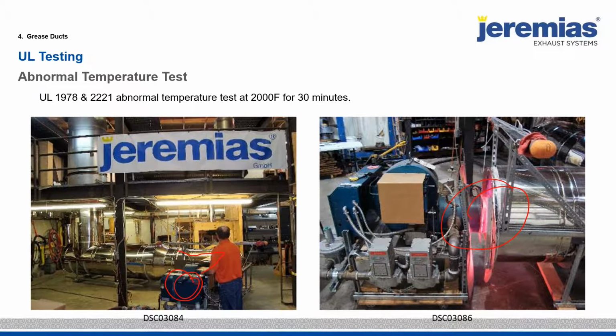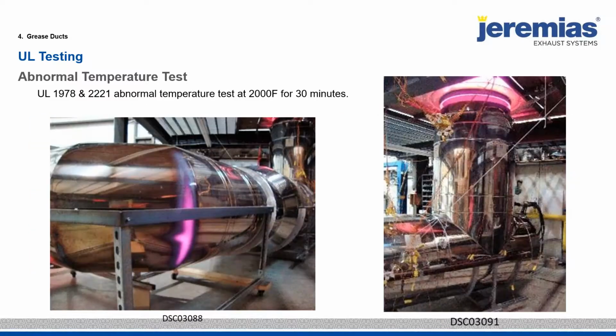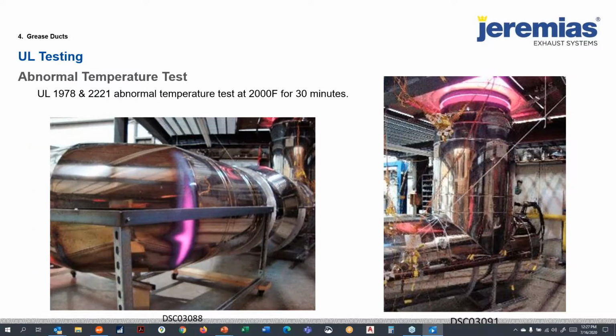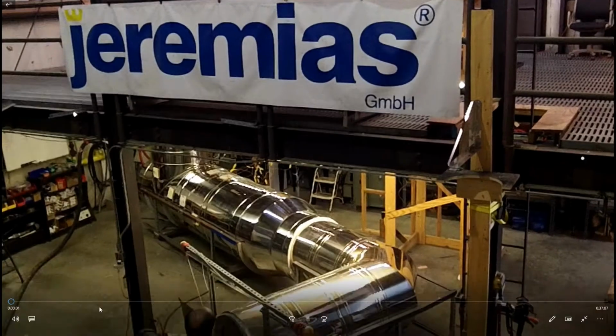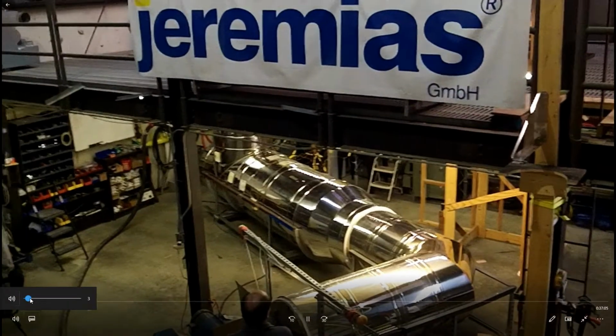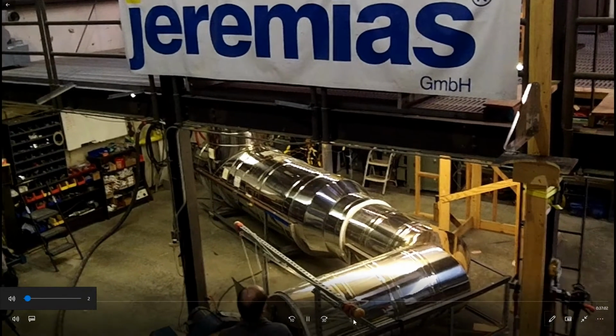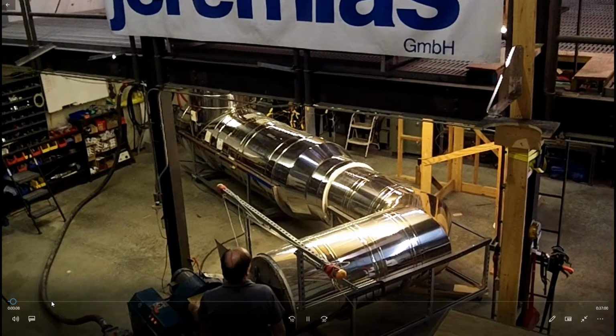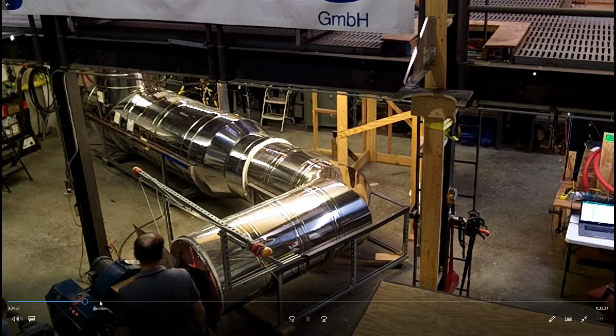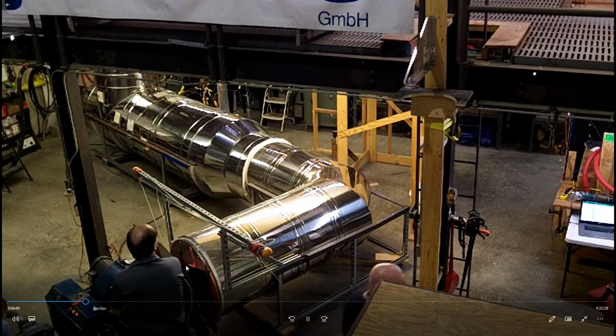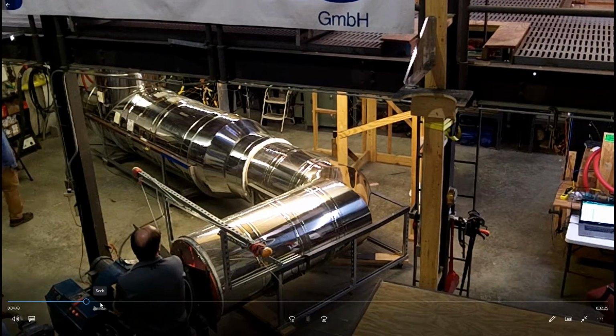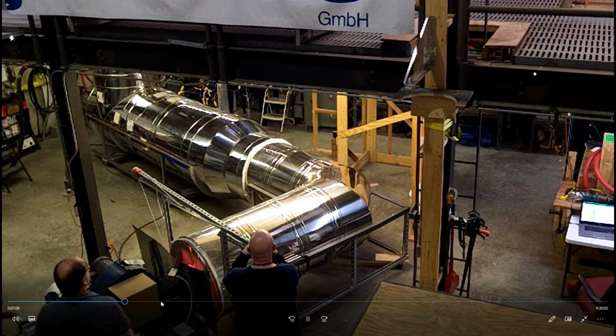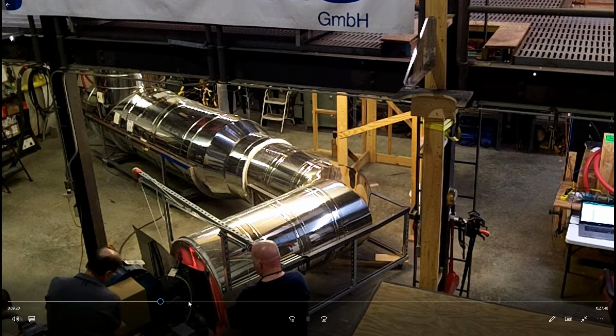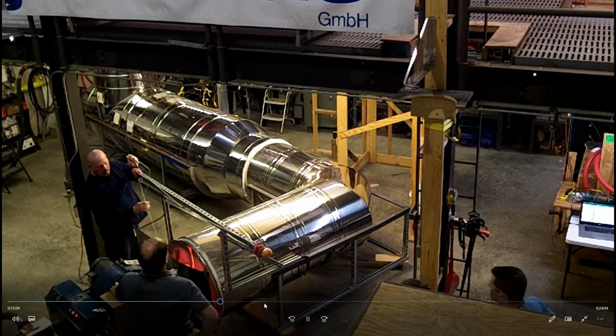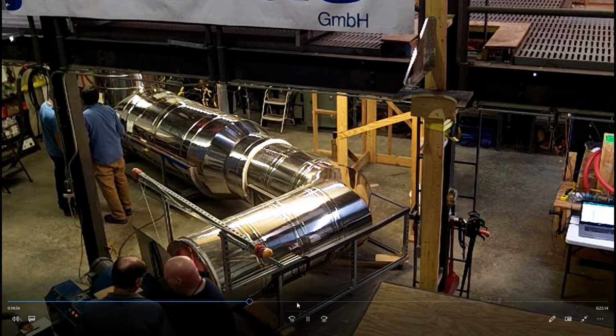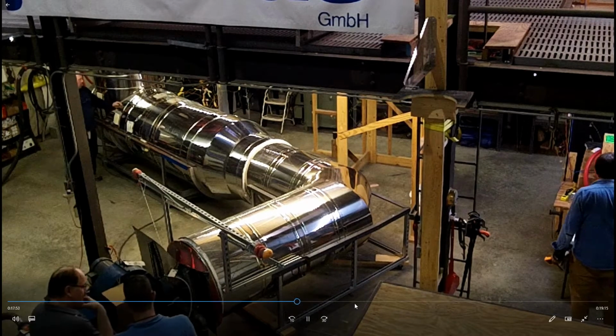This is a very sobering type of system to hear. It sounds like a jet engine. I'm going to get into the video here. And what we have actually is a 37-minute video. So I'm going to fast forward this very quickly. You can see that 10 minutes into the video, we get the red hot flue gases on the flue gas generator. And this video is during the actual UL witnessing of the test. So you see the guys walking around, making tweaks to the burner, measuring the skin temperatures.